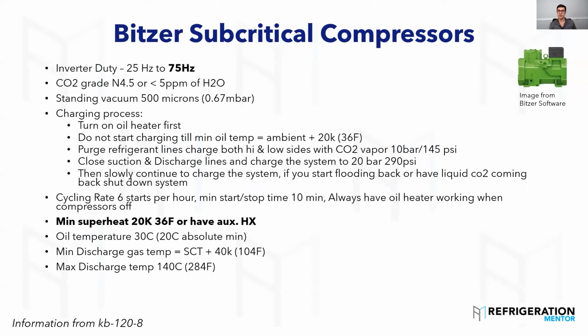Okay, so this is the Bitzer subcritical compressor. I didn't want to go through it step by step, I just wanted to do that one. A little bit different: their max on the subcritical is 75 hertz, not 87. All the rest of the stuff they really talk about being the same, but the minimum superheat for the subcritical, this is the low temp, is 20K, 36 degrees Fahrenheit. You need to keep that.